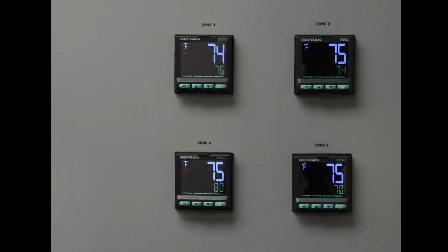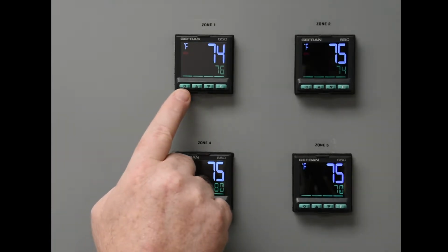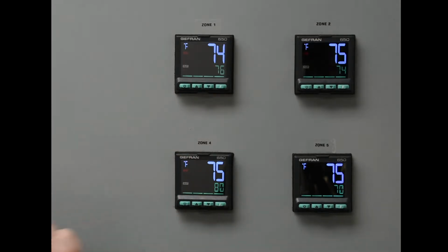In the bottom left is the home or the work mode key. This will function in different ways depending on previous steps. If you are configuring parameters with the quick start, pressing it will return you to the home screen. If you are already at the home screen, pressing this button will toggle the auto tuning function on or off.